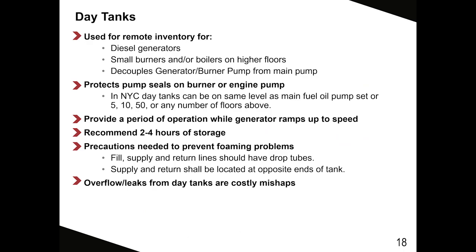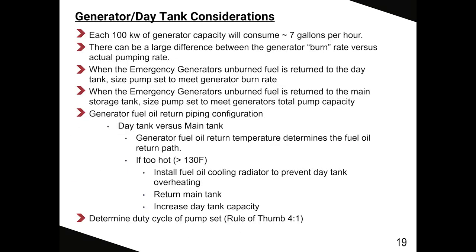For good circulation, space supply and return piping as far apart as possible, each near the bottom of the tank. And you must have a means to prevent overfilling. Day tank piping considerations.